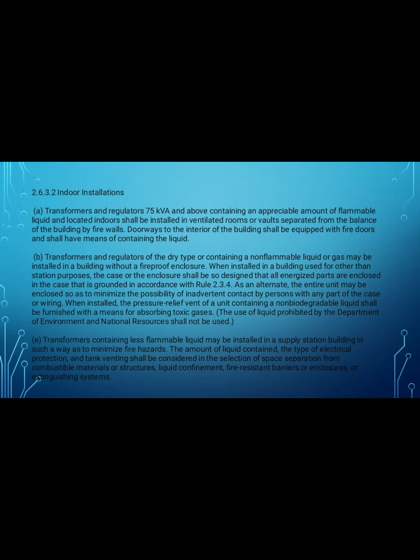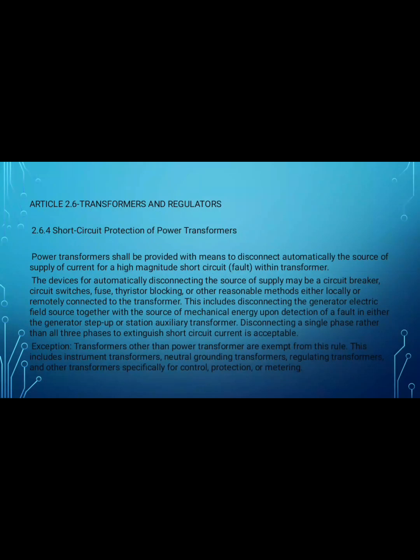(e) Transformers containing less flammable liquid shall be installed in supply station buildings in such a way as to minimize fire hazard. The amount of liquid contained, the type of electrical protection, and tank venting shall be considered in the selection of space separation from combustible materials or structures, liquid confinement, fire-resistant barriers or enclosure, or extinguishing system.